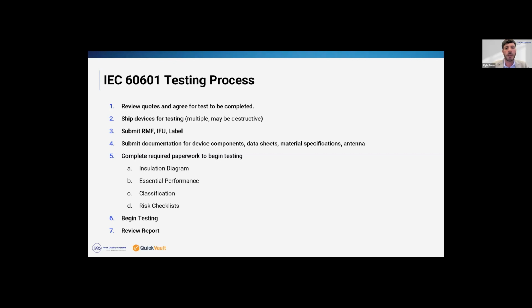They also review, and this is a very key area that not a lot of people realize, other internal documentation, because the 60601 testing and standard also covers it. They'll review your SOPs, specifically around design and risk. They'll review your risk management file to make sure you have the correct risks and hazards identified, as well as mitigation in your file. They'll review your instructions for use and your labeling, because all of these are within the standard and scope of testing.